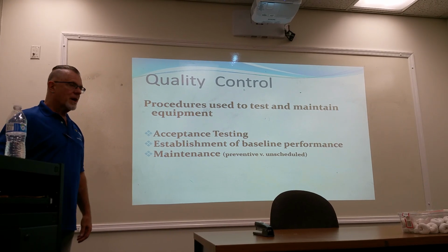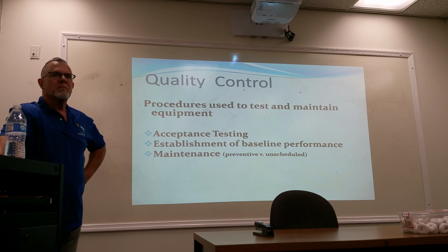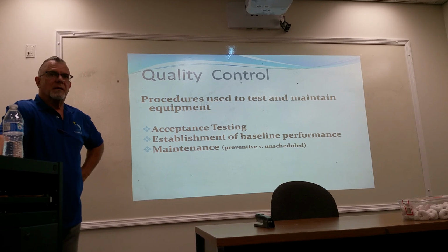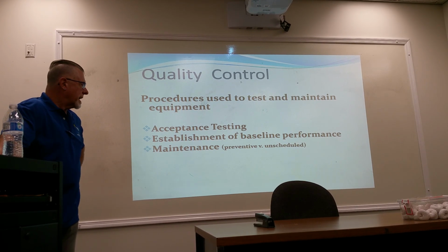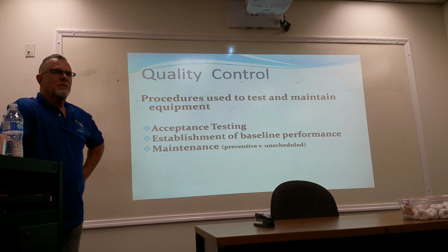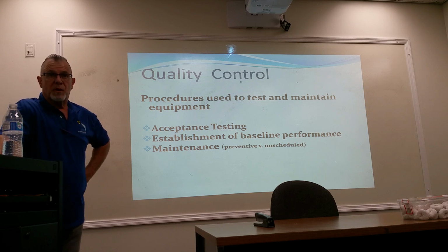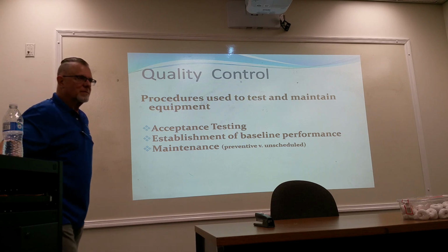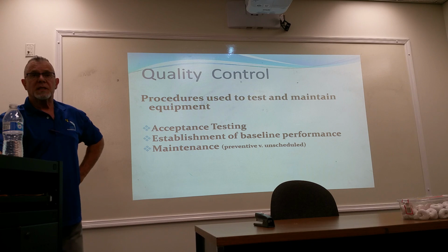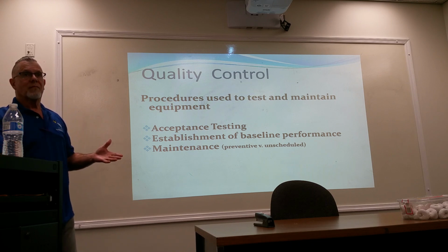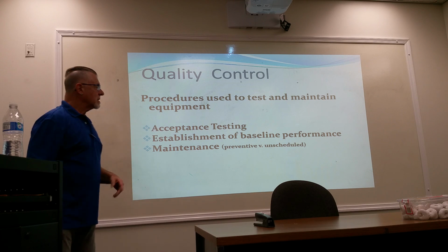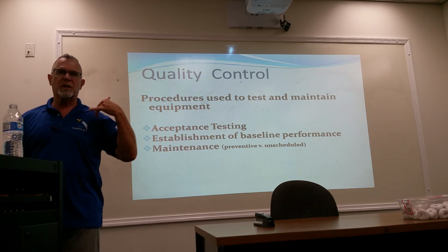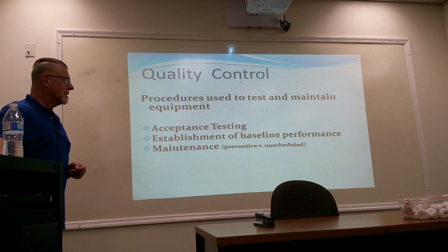And that can be anything from the light bulb in a collimator to an arcing tube, which is no fun, scary, but not particularly dangerous. Buckies that won't move, exposure switches that have a frayed cord, inability to make an exposure. Not detenting. Yeah. On a digital piece of equipment, you have artifacts. That's usually enough to shut a room down. So those are unscheduled maintenance, and that's when you have to put in a service call and get that equipment fixed.